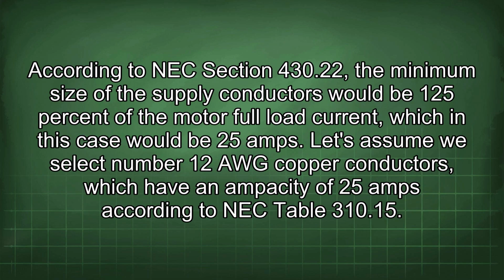According to NEC section 430.22, the minimum size of the supply conductors would be 125% of the motor full load current, which in this case would be 25 amps. Let's assume we select number 12 AWG copper conductors, which have an ampacity of 25 amps according to NEC table 310.15.